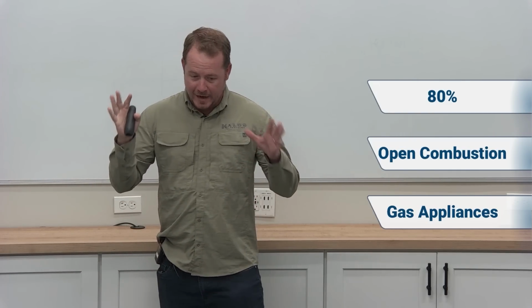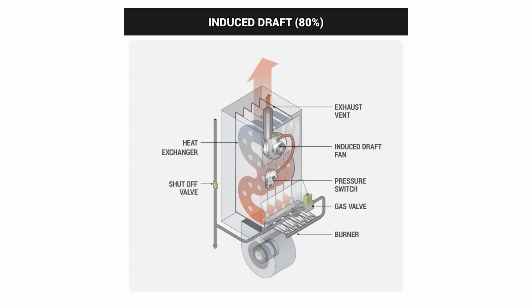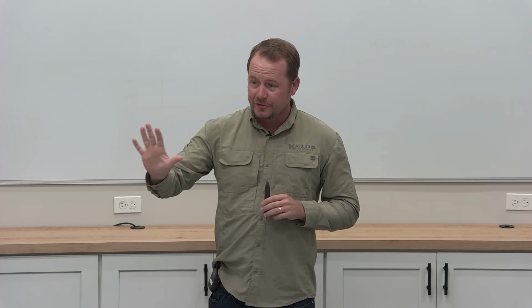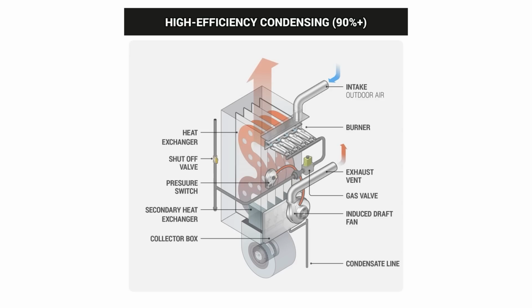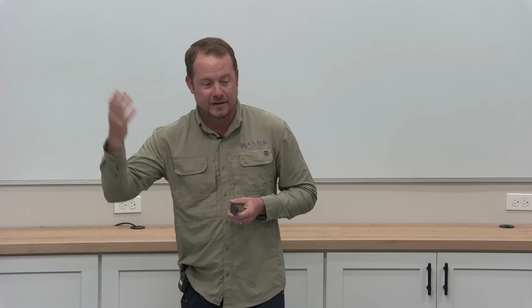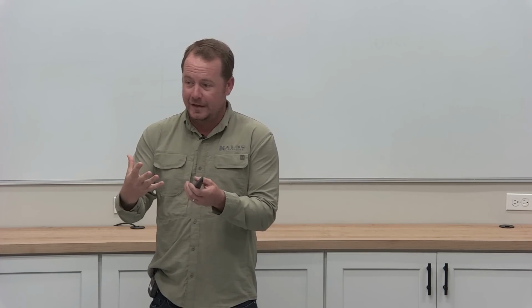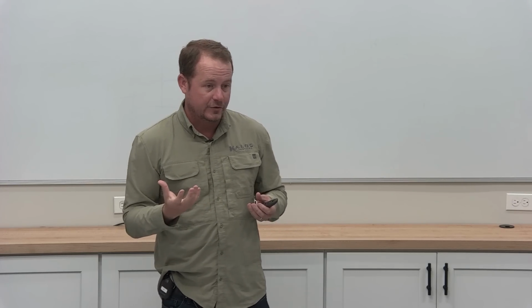In Florida, the air that we use for combustion, the oxygen that we use for combustion on a furnace, comes in through the front of the furnace. If you've ever paid attention to a furnace, you know this has a louvered front, right? In a high efficiency furnace, the air that is used for combustion generally is brought in from the outside through a PVC pipe. So it comes in through a PVC pipe, goes out through a PVC pipe. And that seems crazy because, of course, for us, when we are sending flue gas out of the structure, it's pretty high temperature still, and that's why we have to use metal flue. And that's because with these high efficiency furnaces, they squeeze so much heat out that the actual discharge is low enough temperature that you can discharge it through PVC.